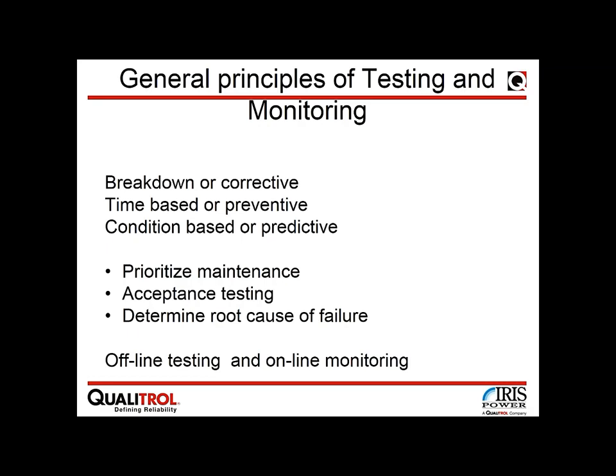To help operators recognize differences between supposedly identical machines, there is condition-based or predictive maintenance. This is based on installation of certain sensors used for assessment of the machine while it is running. Data collected this way can determine maintenance priorities, support acceptance testing, and in unfortunate cases assist with root cause analysis of failures.